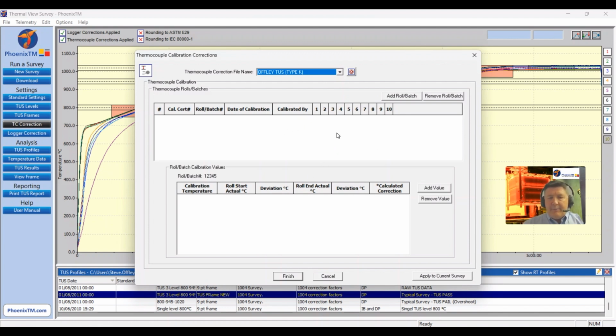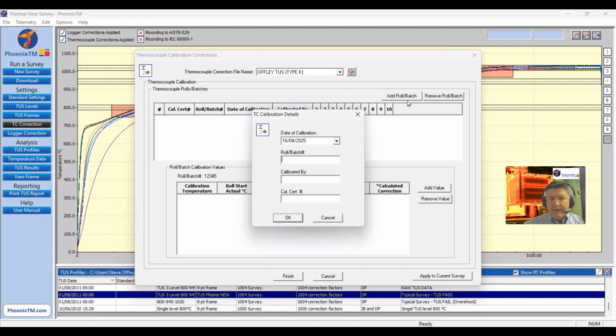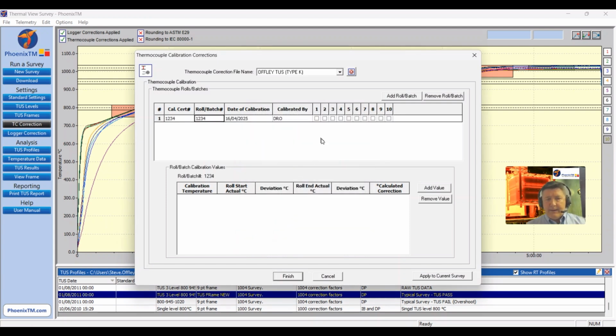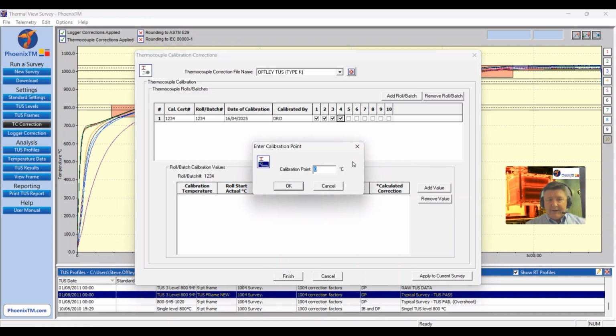So you see the table is empty. So what I need to do first of all is add the batch of cable that I want to add my calibration data for. The calibration date, 16th of the 4th, 2025. I'm going to call it 1234, calibrated by myself, and the calibration certificate is 1234. Okay. Now for this batch, I know that the first 4 thermocouples I'm going to use, channels 1 to 4, are from that batch. So I'm going to add a generic 3-point calibration.